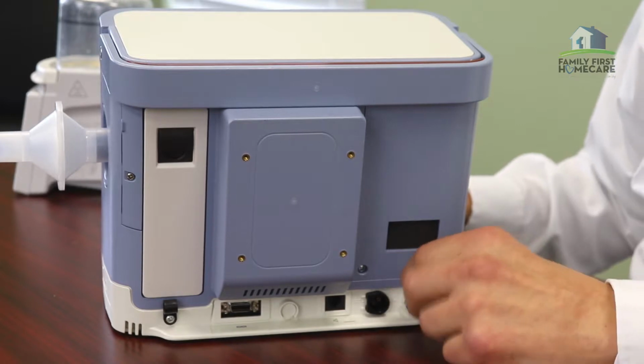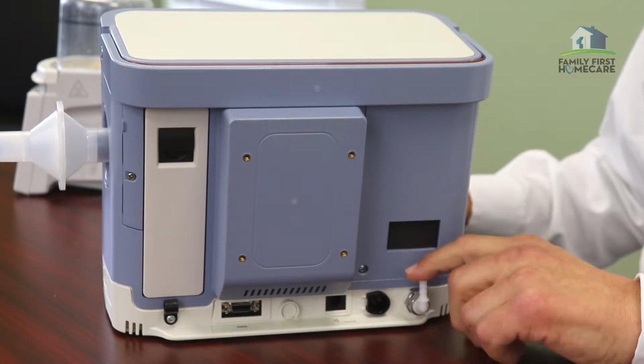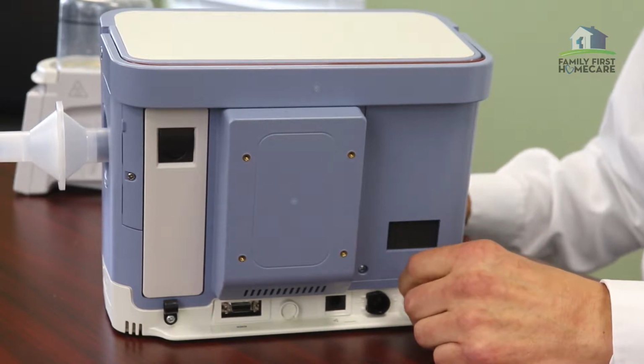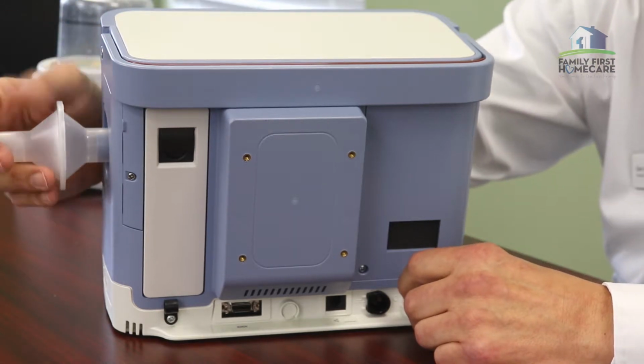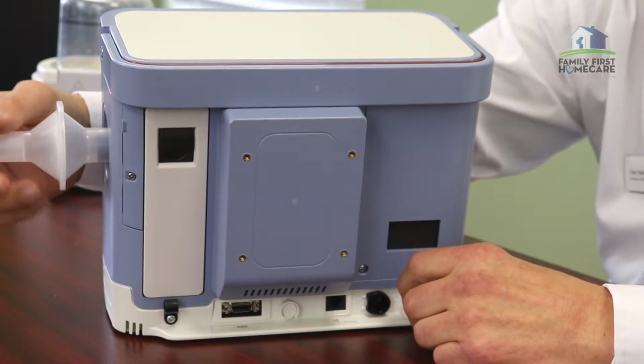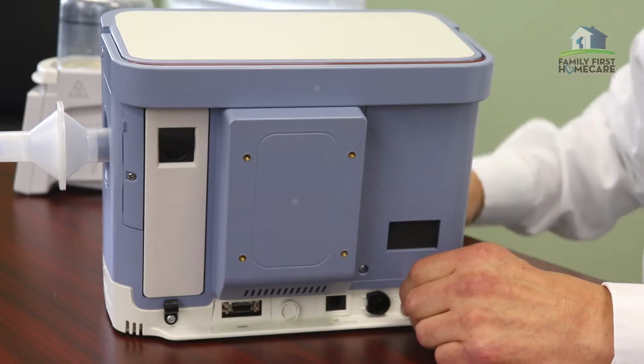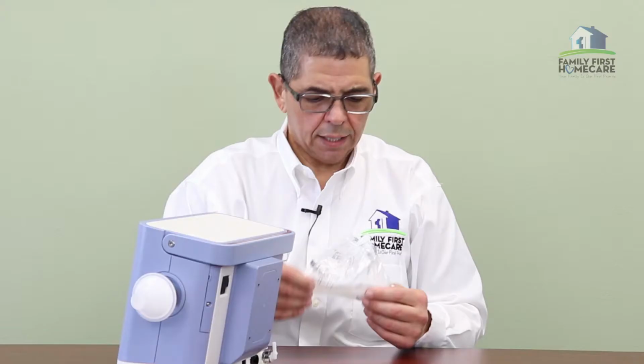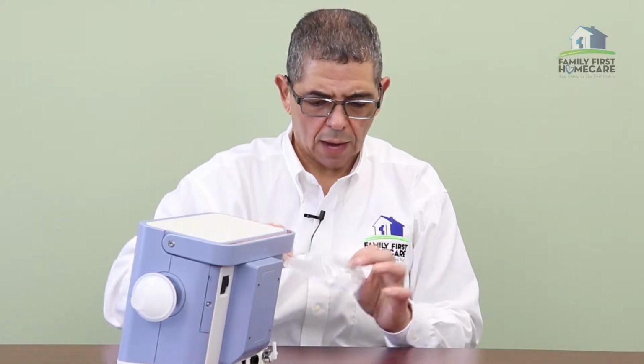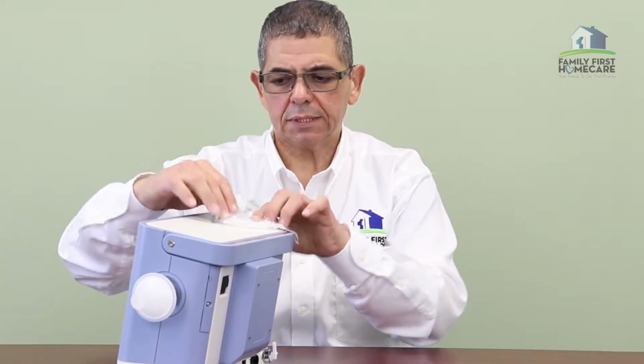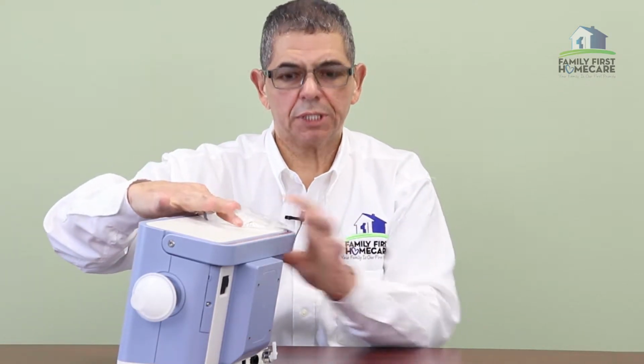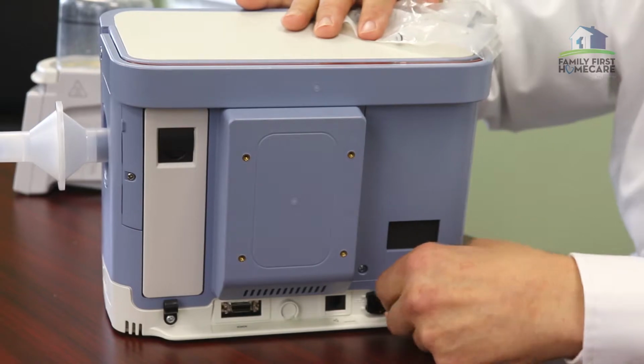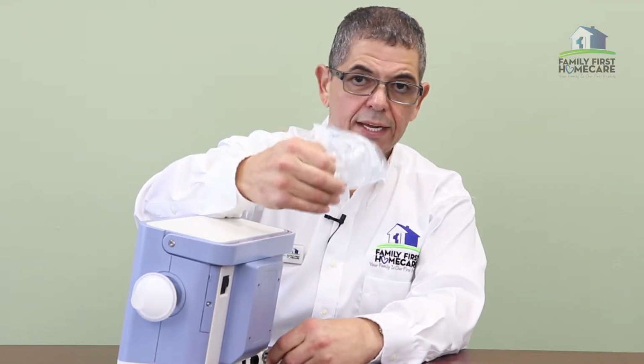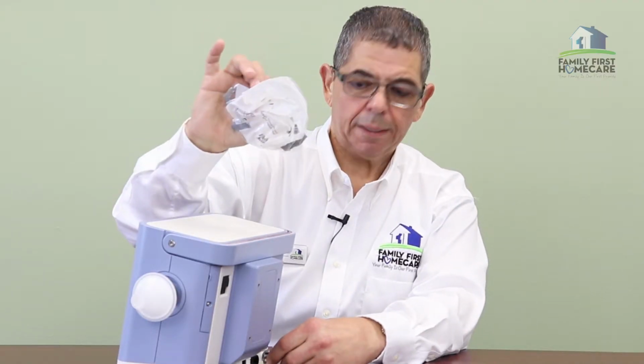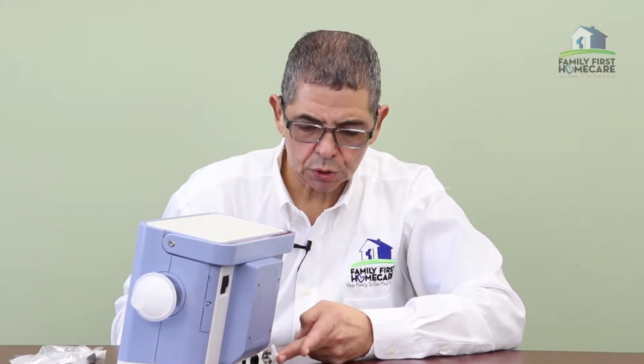This is very important. These break off. Oxygen must run through the machine again so it mixes with the flow to make sure it gets a nice even flow and doesn't distort any of the settings that are in the machine. They come in a package of 2. I would even take one and tape it right on the top of the machine, so if this should break, you have it. So make sure that you have these extra ones from the DME, because the oxygen must run through the port.